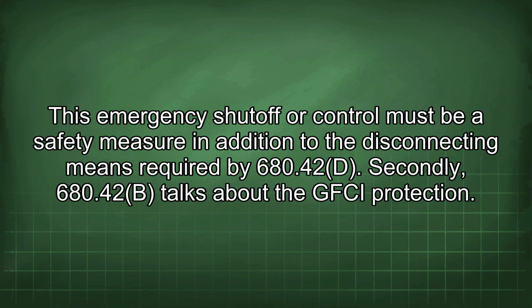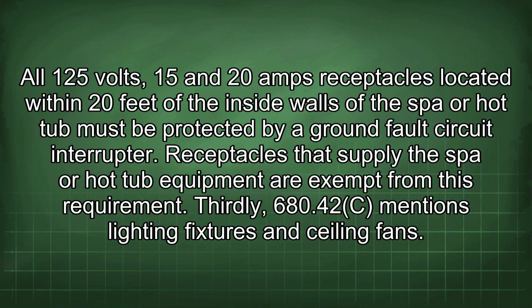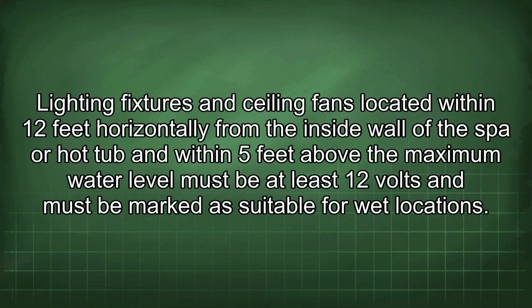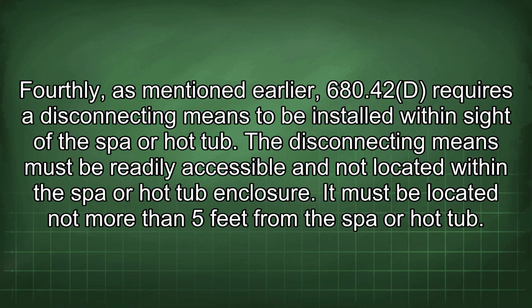Secondly, 680.42(B) talks about the GFCI protection. All 125 volt, 15 and 20 amp receptacles located within 20 feet of the inside walls of the spa or hot tub must be protected by a ground fault circuit interrupter. Receptacles that supply the spa or hot tub equipment are exempt from this requirement. Thirdly, 680.42(C) mentions lighting fixtures and ceiling fans. Lighting fixtures and ceiling fans located within 12 feet horizontally from the inside wall of the spa or hot tub and within 5 feet above the maximum water level must be at least 12 volts and must be marked as suitable for wet locations.